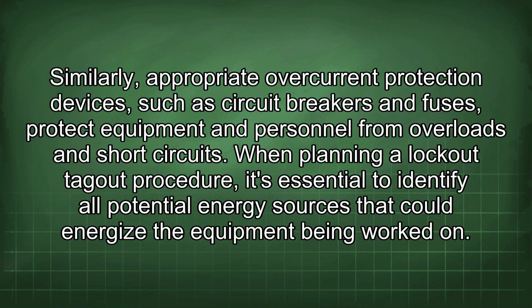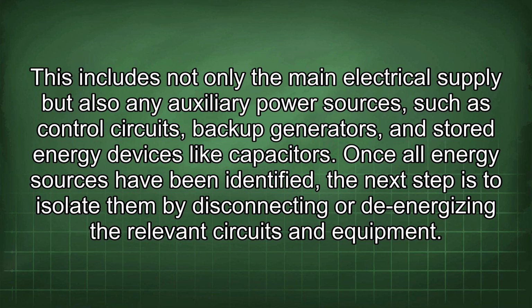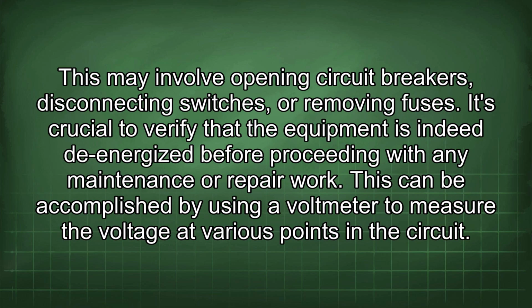When planning a lockout tagout procedure, it's essential to identify all potential energy sources that could energize the equipment being worked on. This includes not only the main electrical supply but also any auxiliary power sources such as control circuits, backup generators, and stored energy devices like capacitors. Once all energy sources have been identified, the next step is to isolate them by disconnecting or de-energizing the relevant circuits and equipment. This may involve opening circuit breakers, disconnecting switches, or removing fuses. It's crucial to verify that the equipment is indeed de-energized before proceeding with any maintenance or repair work. This can be accomplished by using a voltmeter to measure the voltage at various points in the circuit.